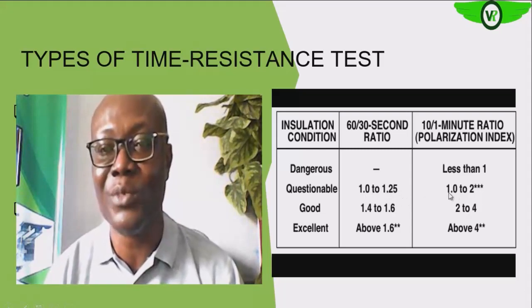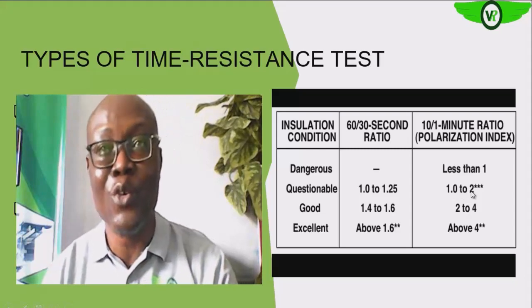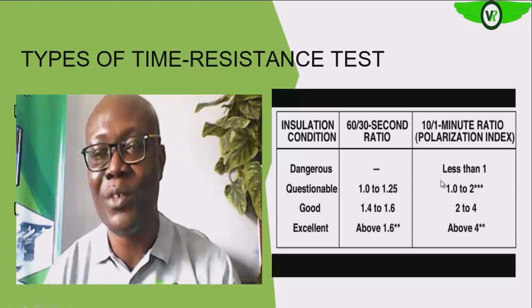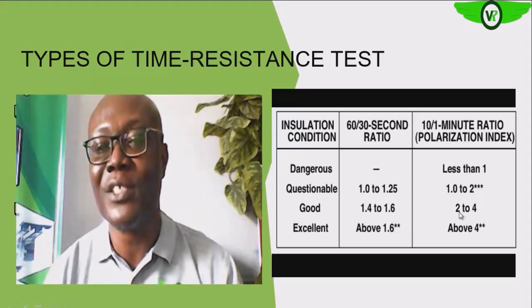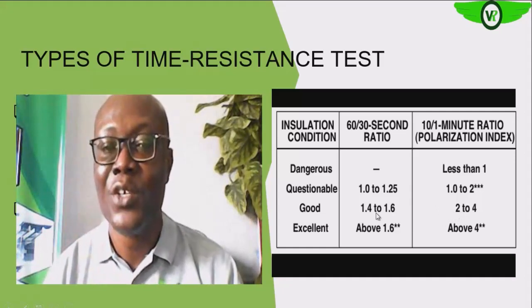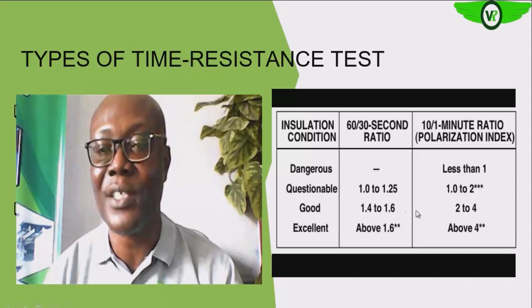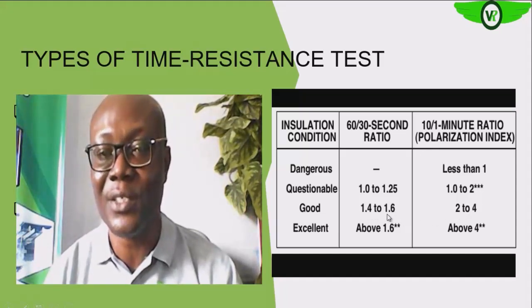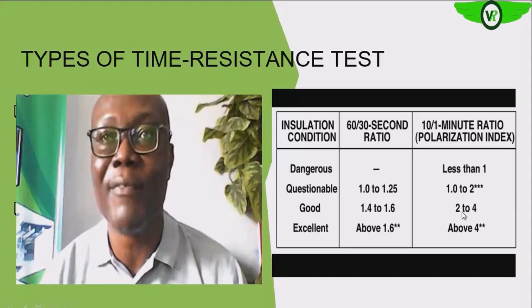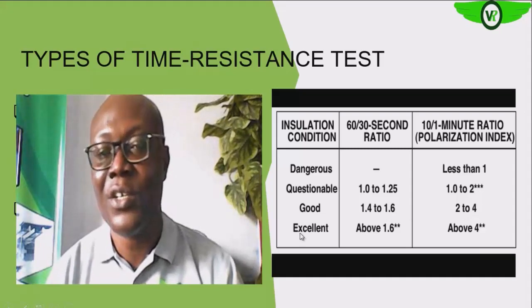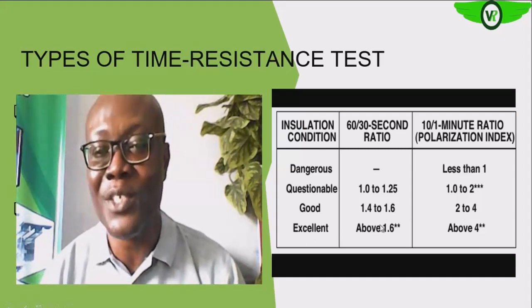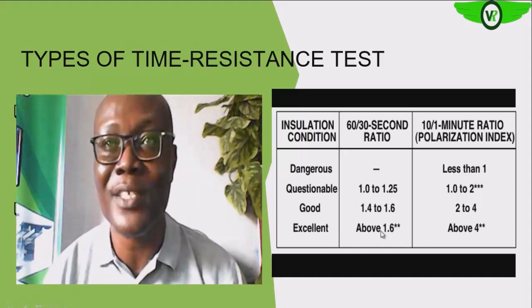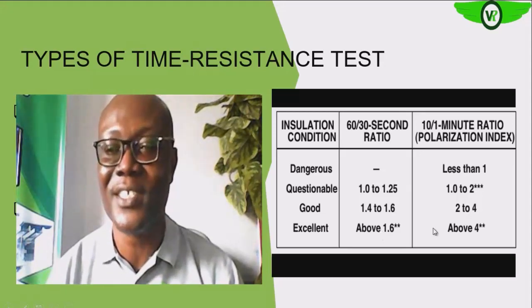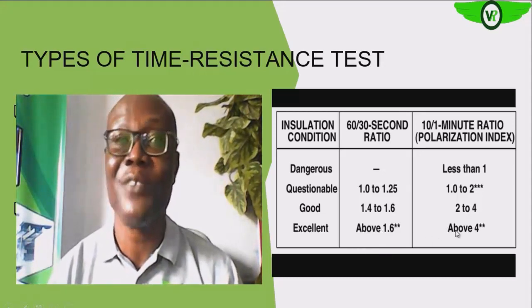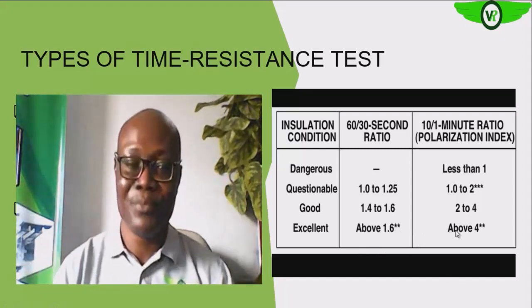Are you getting there? For polarization index between 1 and 2, it's also questionable, but for low voltage equipment, it could be acceptable. But for medium and high voltage equipment, you expect it to be very high. Are you getting it? Anything from 1.4 and above, 1.6 and above for the DAR test is okay. Then between 2 and 4 for the polarization index test is also okay. So you will be very confident of the insulation when you have above 1.6 or 2 for your DAR test, that is the dielectric absorption test. And if you have above 4, that means the insulation is superb for your polarization index test.